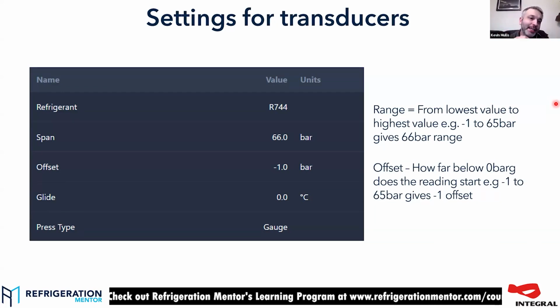You've got to get the right readings into the controller if you want the right superheat calculation, if you want the right temperature control. If you push that resistance up, the reading will go up, and you will end up with a chill room that's too cold, or you'll end up never meeting set point if it's a freezer.